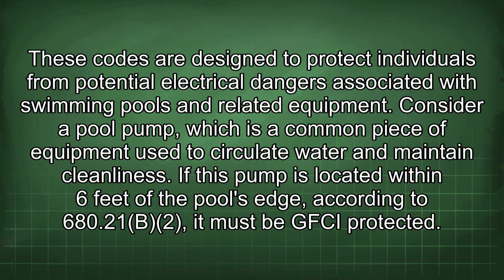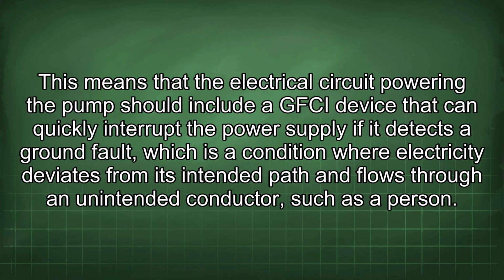Consider a pool pump, which is a common piece of equipment used to circulate water and maintain cleanliness. If this pump is located within 6 feet of the pool's edge, according to 680.21(B)(2), it must be GFCI protected. This means that the electrical circuit powering the pump should include a GFCI device that can quickly interrupt the power supply if it detects a ground fault, which is a condition where electricity deviates from its intended path and flows through an unintended conductor, such as a person.